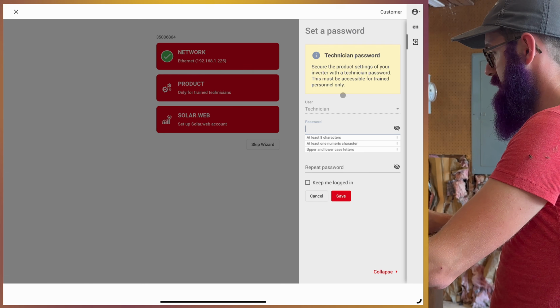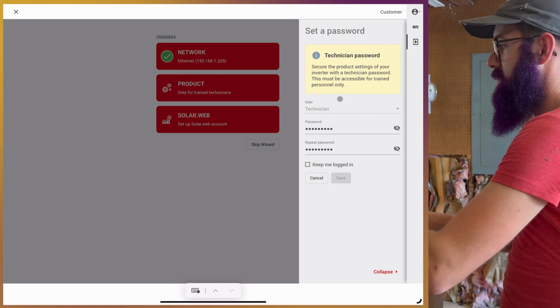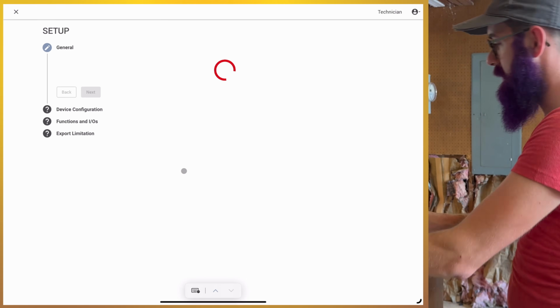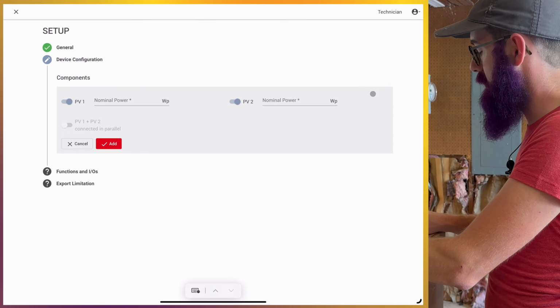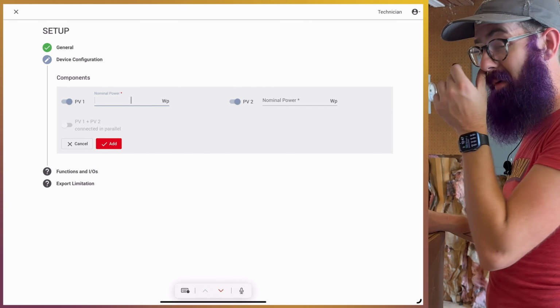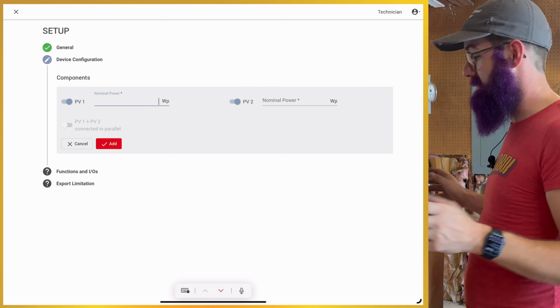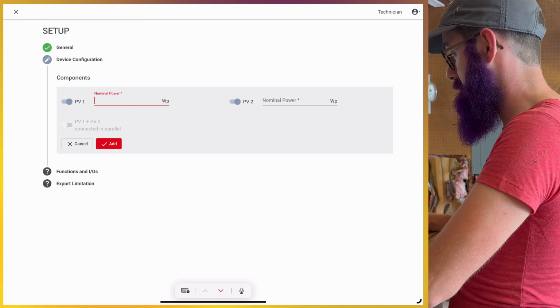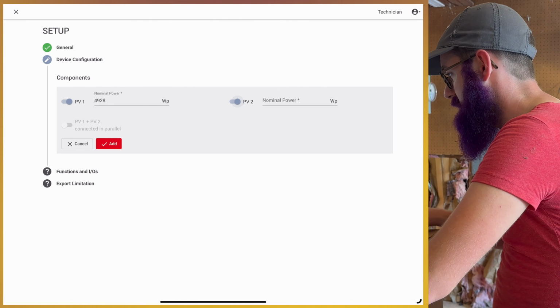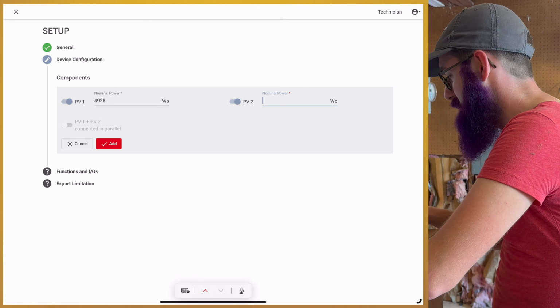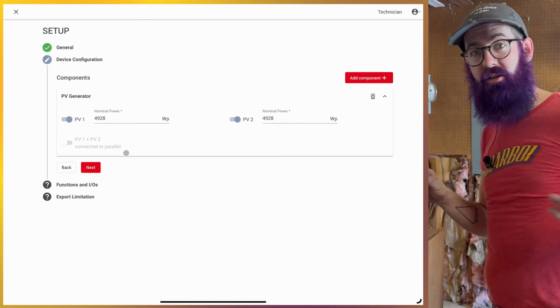After we set up the network, we need to set up the technician password. And once we get to device configuration, this is where you'll want to know how much power the entire system can produce. For ours, it is 4928 per MPPT, that's what the panel wattage is nominally.